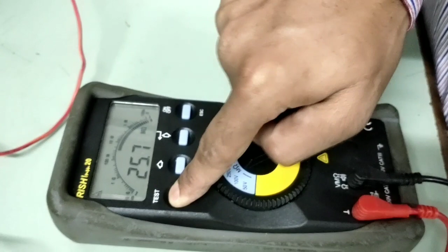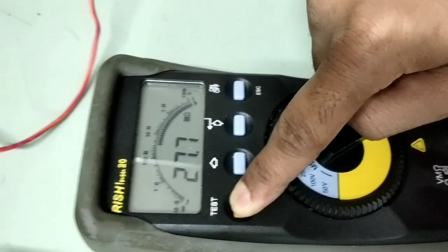Now what I will do, I will just press the test point of this meter, and accordingly we will get the reading. You can see that its value is shown there, 26.7 megaohm. So the insulation resistance of this cable is 26.7 megaohm, insulation between two conductors.